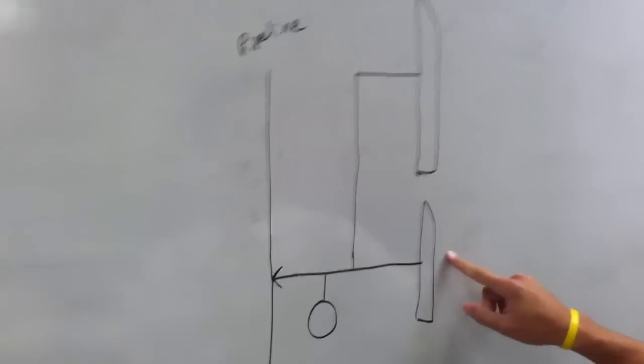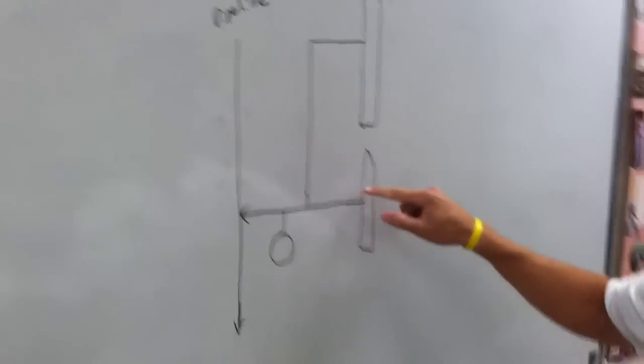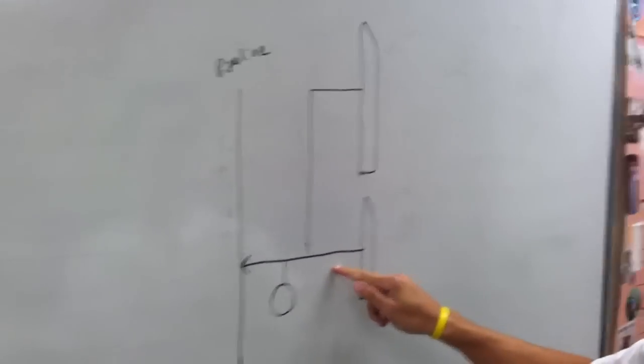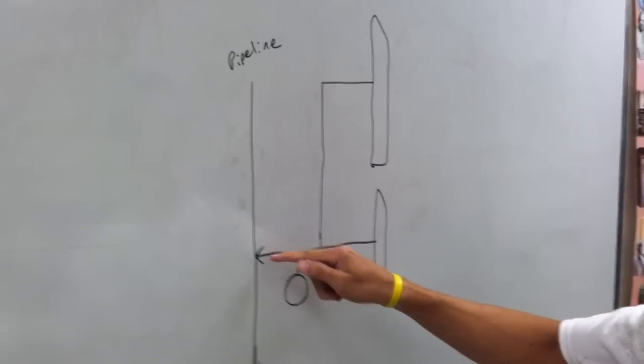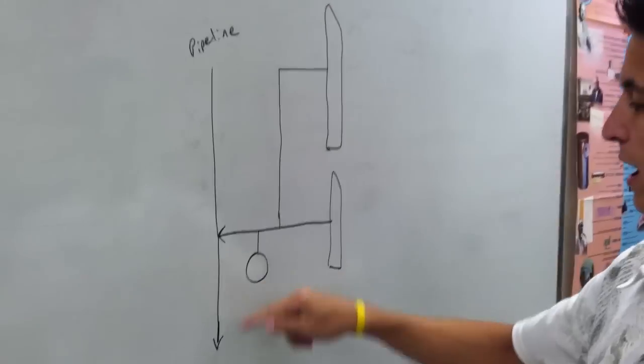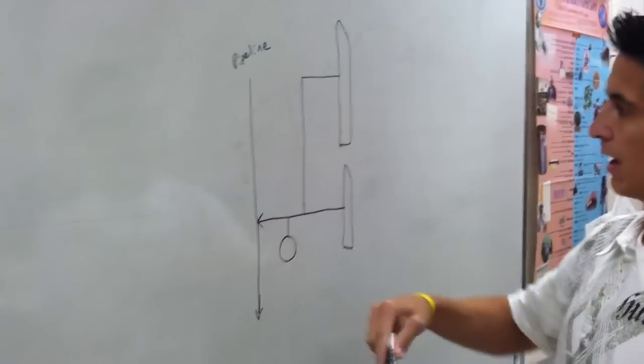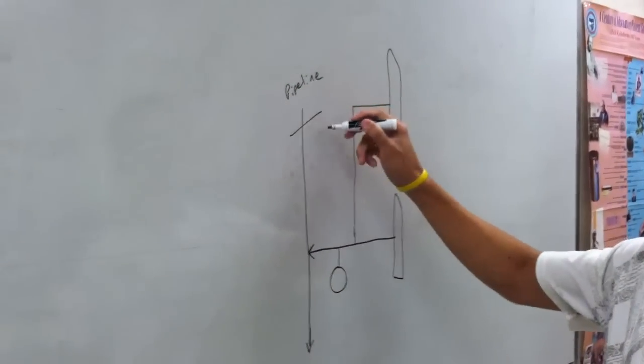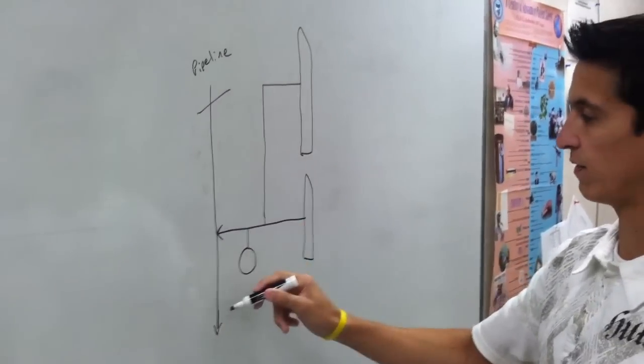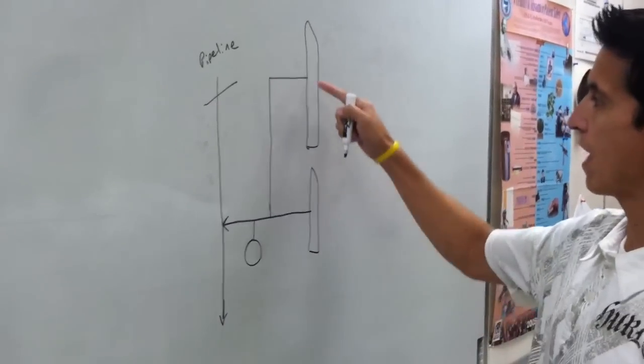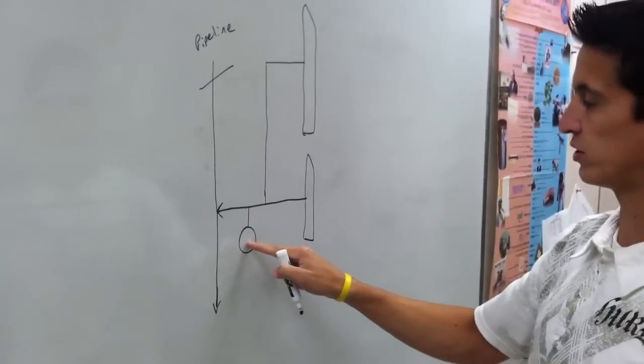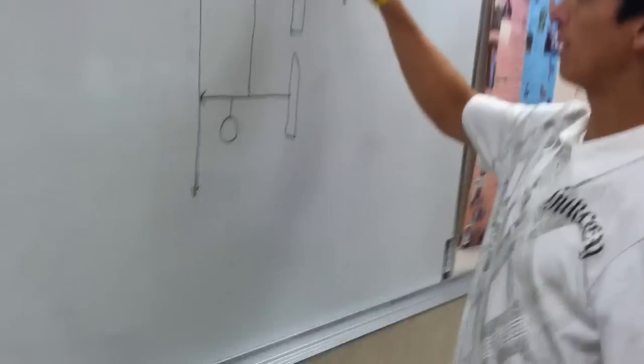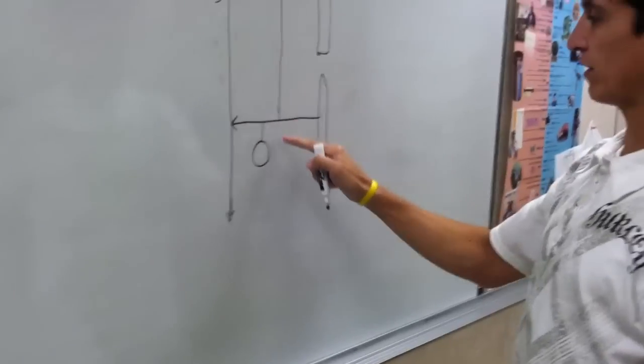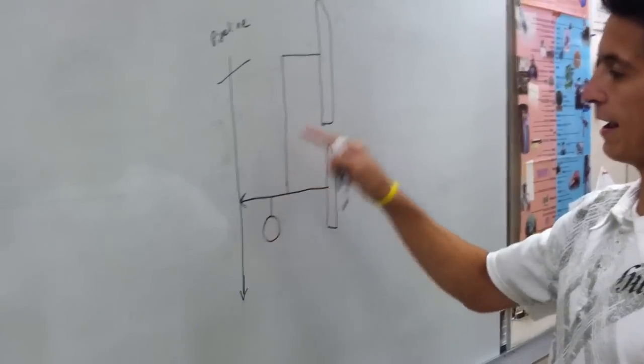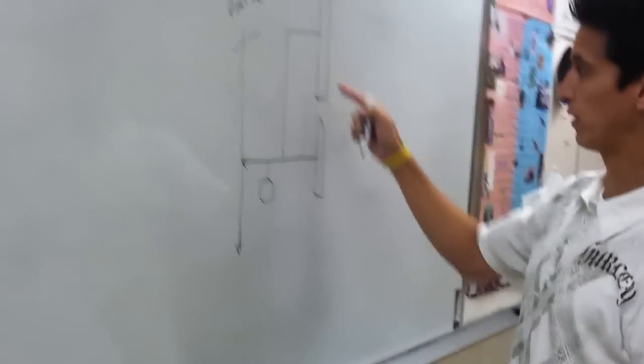When you open up the first cylinder, it pressurizes all of these lines. The only way to relieve that pressure is to allow it to flush out of the system. However, this valve will not open up until we disconnect the pipeline, and then the pressure on this side will be less than 50 psi when we push the O2 flush valve. That will release all this pressure here, bring the gauge down to 0, and then we can open up our second cylinder. That's going to pressurize everything, give us a second reading, and that's how you get the 2 different readings for 2 cylinders. And I'm going to prove that right here.